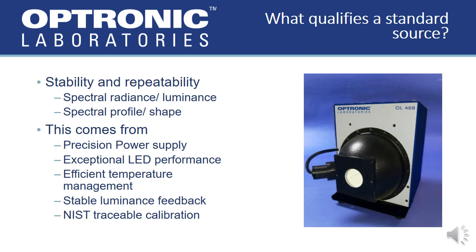The OL-469 is a NIST traceable calibration standard of radiance, luminance, and chromaticity. A standard calibration source must be stable with a high level of repeatability. This repeatability comes from several factors. A precision power supply must be used to drive the currents to high-quality LEDs in order to ensure an exceptional LED performance.